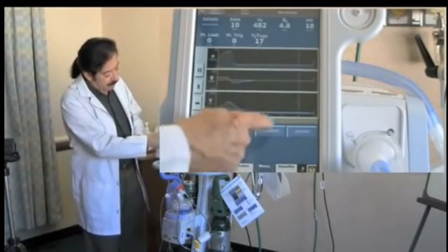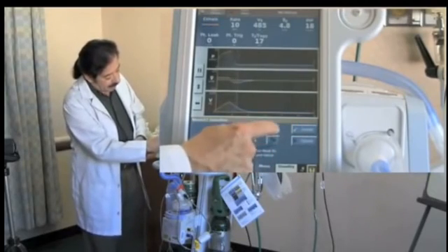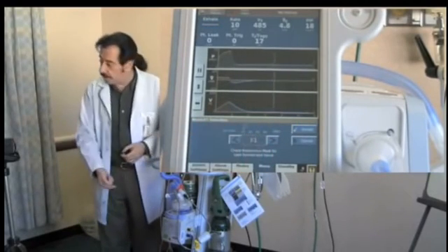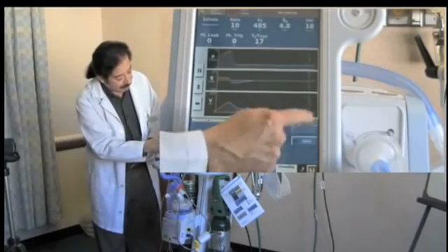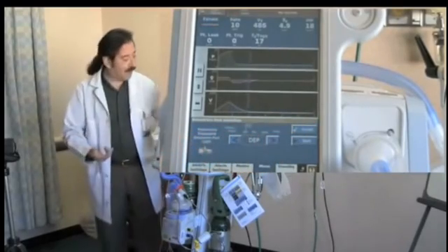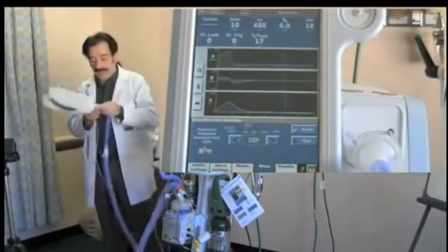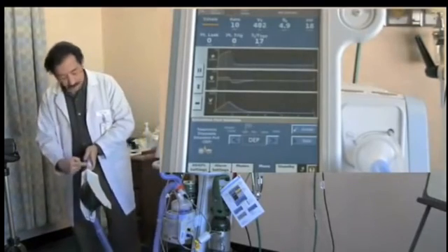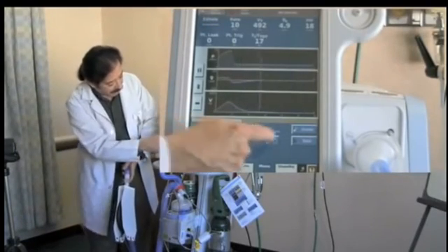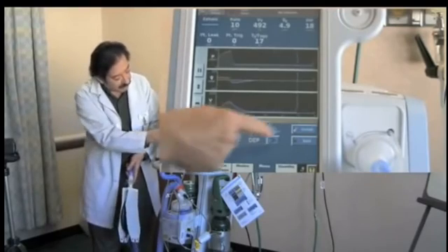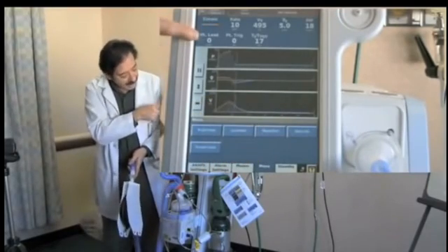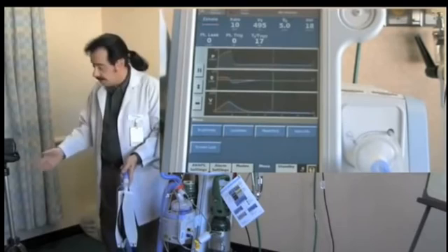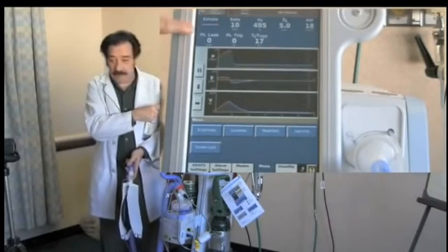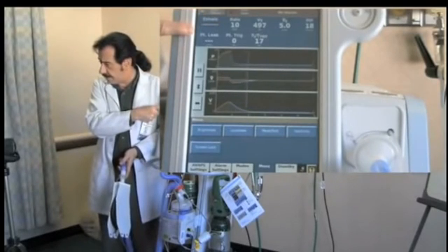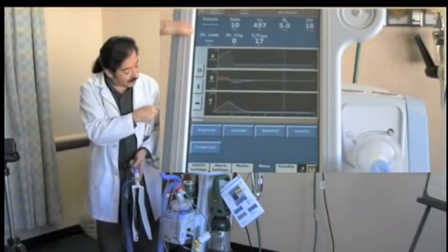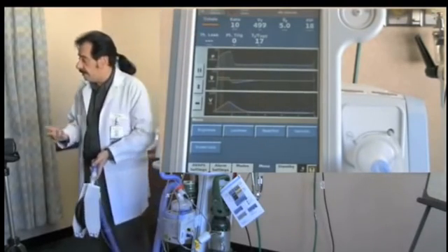So you go to Menu, Mask Port, tell it that you're using an interface that has the number 1 on it, and accept that. And then it says, what kind of whisper valve are you using? And that is the Respironics disposable valve here. So I dial that in, and it even shows me a little picture of it. Accept that. Now it says, okay, that's all I have to do. Okay? It is distinguishing what the patient leak is from the leak in the whisper valve, and it knows exactly what the leak in the whisper valve is. Okay? So it says there's no leak here.